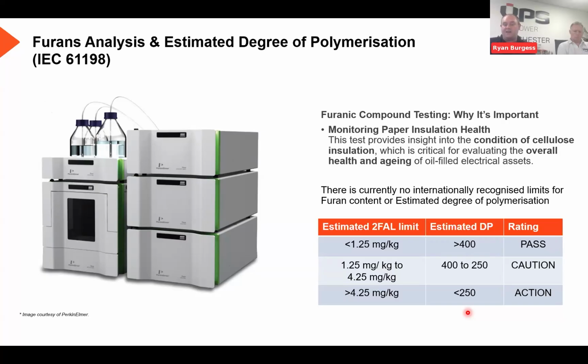But it's not just a simple case of, oh, we'll put new oil in, because at that point, you're going to lose the information that you've collected from the aging process, and it will reset. So the data will go, oh, your furans are back to normal, but you've just lost all your data because it hasn't had time to re-equilibrate. So your paper is still aged. Just by replacing the oil, you're not replacing the paper or re-aging the paper. Have you got anything else to add on furans, Andrew?